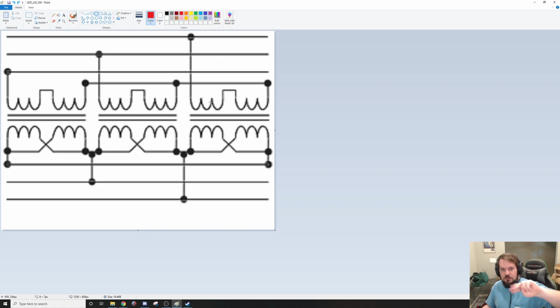So there's two ways a transformer can be wired, and then those two ways can be wired as high voltage or low voltage. So let's say these are all 120 volt, or let's say these are 240 volt coils. Wiring them like this in series, so the current has to flow through both of the coils, will make it a 480 volt coil.